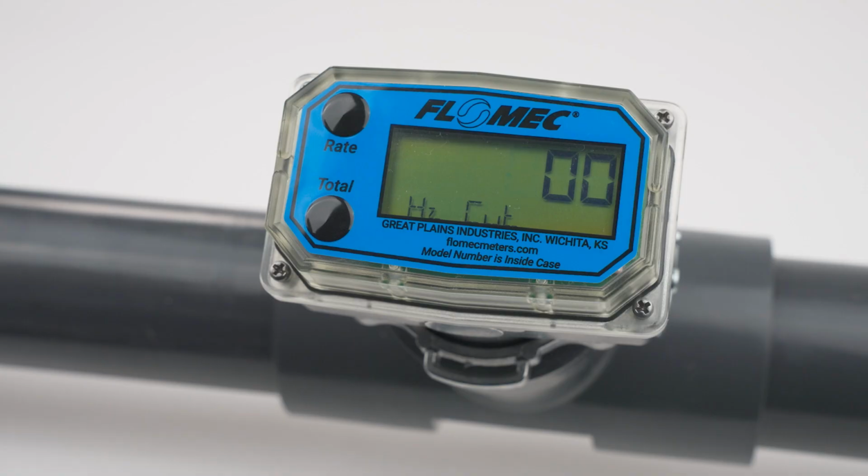Next, the meter will prompt you to select a low-frequency cutoff. This will enter a minimum allowed pulse input frequency to filter out any low-frequency input pulses which can be generated when the meter is subject to mechanical vibrations. These vibrations could cause the Totalizer to add phantom volume to the displayed totalization values.